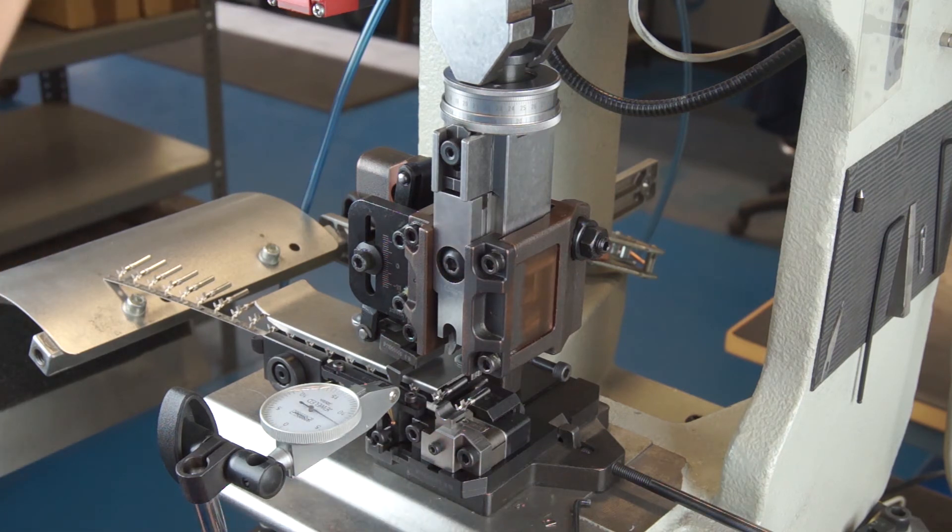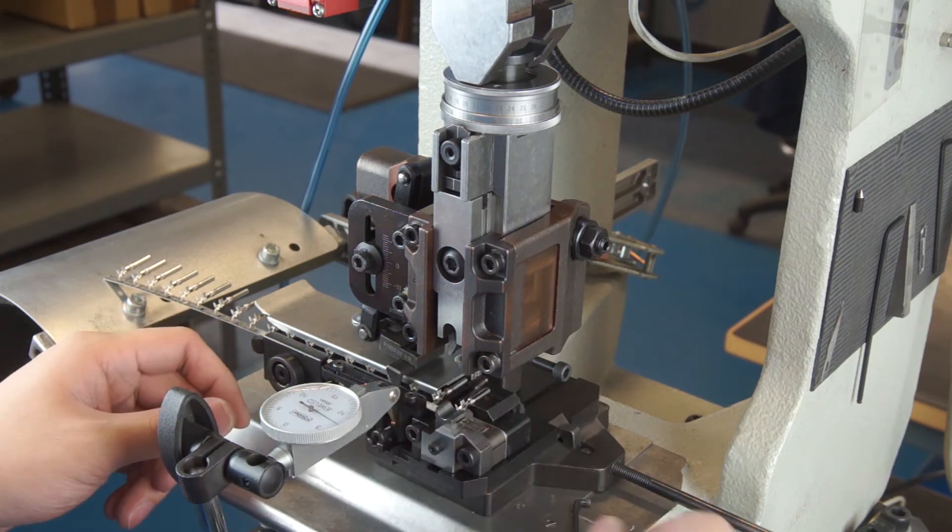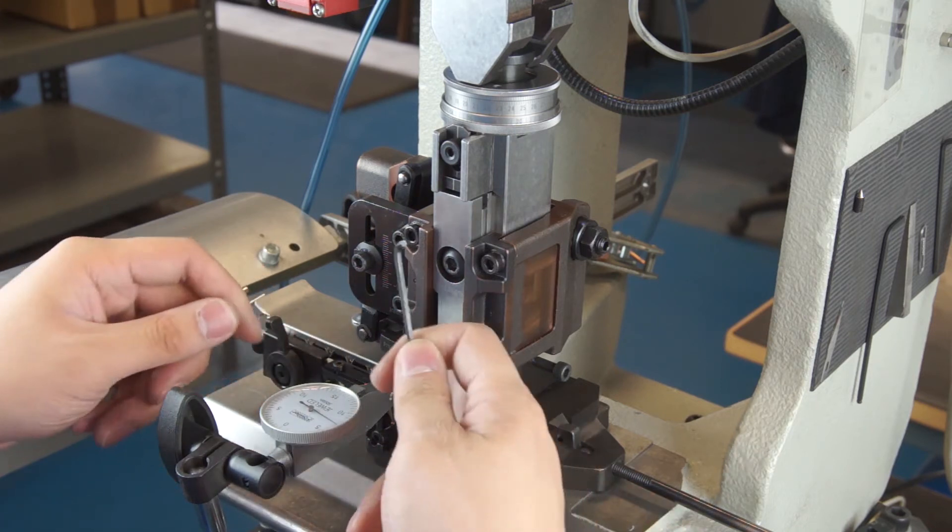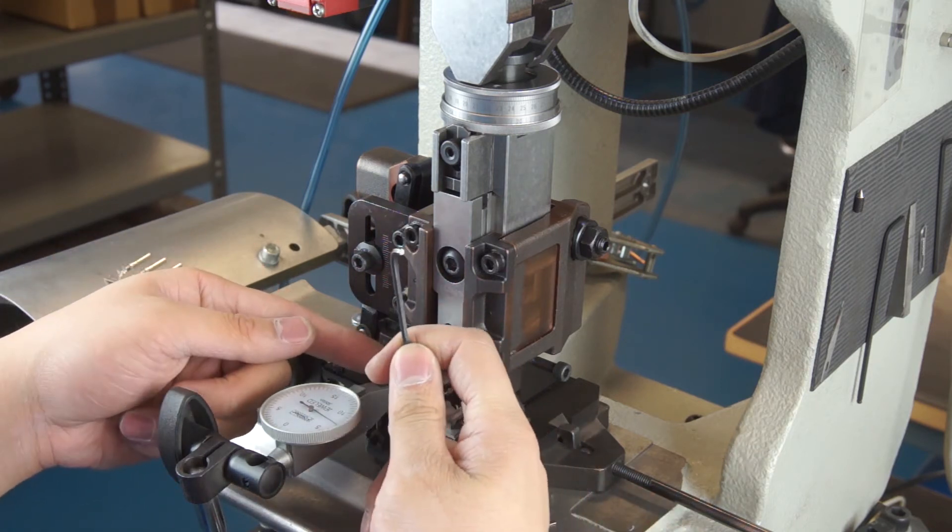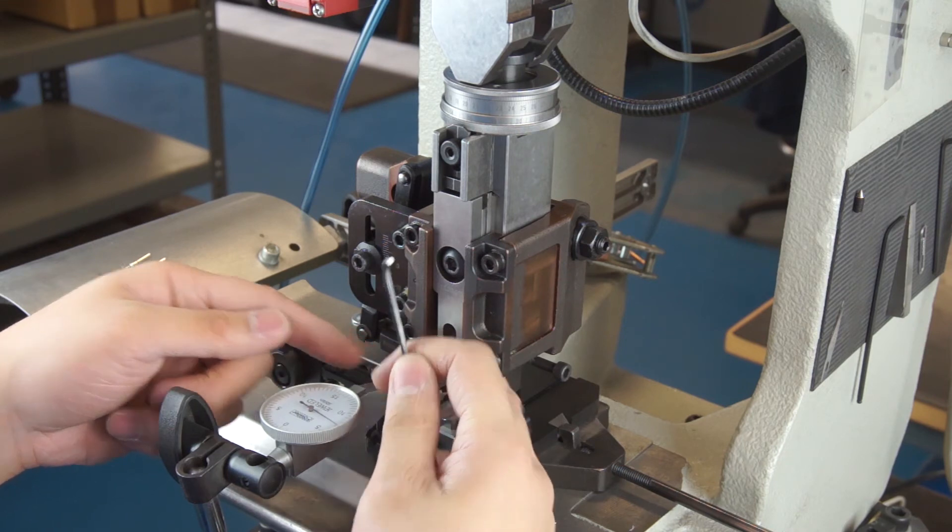Once you have the locking wedge locked back down, the feed finger will need to be re-centered. To do this, visually re-center it in the left guide and tighten the magnet screw, being careful not to move it.